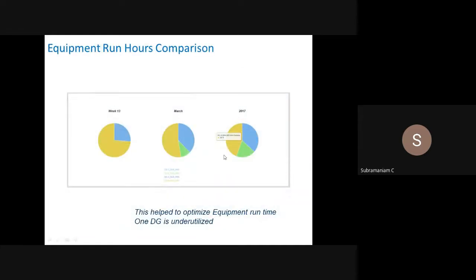And this is a DG set, for example. We have 3 DG sets. So if you see here, on 3rd 2017, DG 1 and 2 have worked equal run hours, but DG 3 has not run. It has run only half of DG 1, which means there is some problem with that DG. The owner has paid the same money, but there is some problem with it, because of which the operator is not running it. So we can fix the problem, why it is happening, so that equal run hours means equal wear and tear, equal maintenance for all the DG sets.